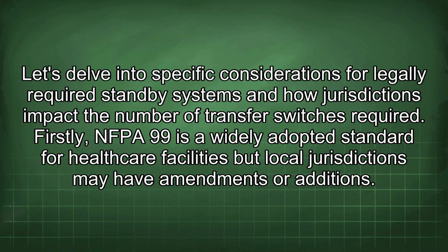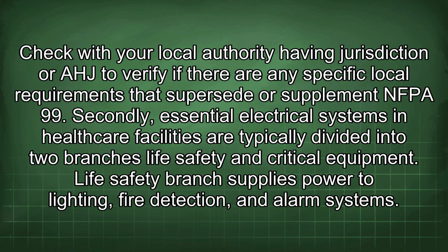Let's delve into specific considerations for legally required standby systems and how jurisdictions impact the number of transfer switches required. Firstly, NFPA 99 is a widely adopted standard for healthcare facilities, but local jurisdictions may have amendments or additions. Check with your local authority having jurisdiction or AHJ to verify if there are any specific local requirements that supersede or supplement NFPA 99.